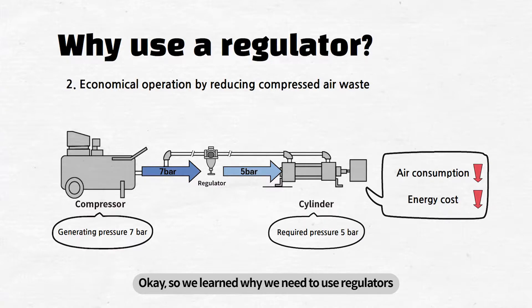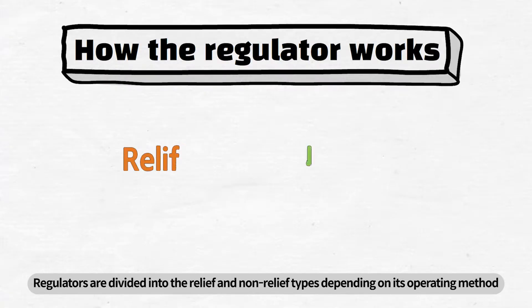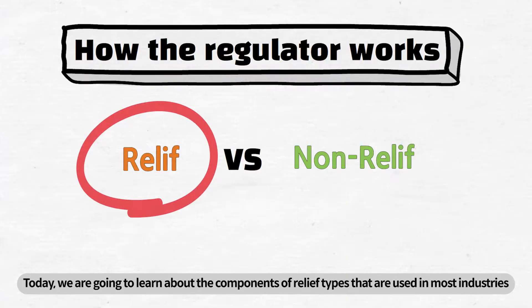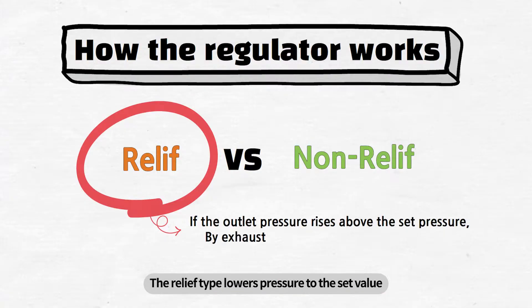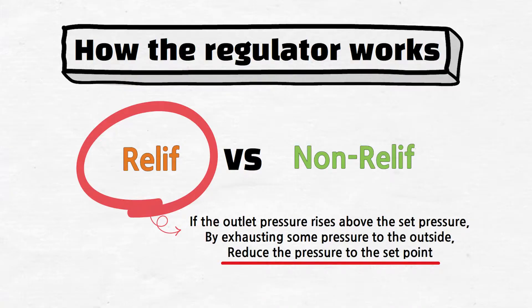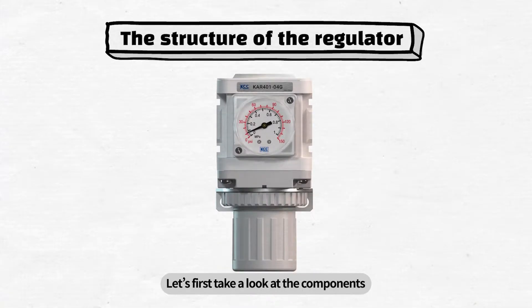So we learned why we need to use regulators. Now let's take a look at the internal components and operating principles of regulators. Regulators are divided into the relief and non-relief types depending on their operating method. Today, we are going to learn about the components of relief types that are used in most industries. The relief type lowers pressure to the set value by discharging the pressure that is in excess of that set in the outlet pressure.